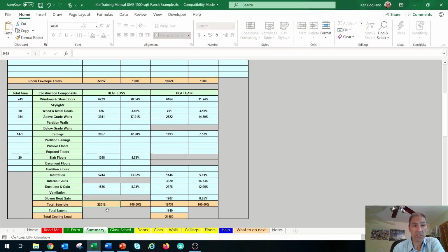And I told you the sizes that I would choose. I would want a 40,000 BTU furnace and a 36,000 BTU or 3-ton air conditioning system. And that would be me if it was my personal residence. What would you choose? Do you agree with that assessment that I'm making? If not, please leave your description down below of what size unit, because that's the whole reason that you're doing this Manual J, to determine what size HVAC and heating this residence requires.